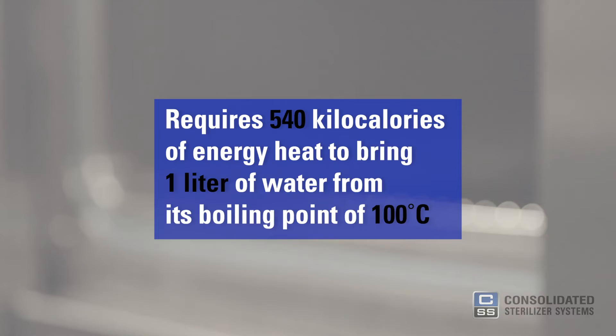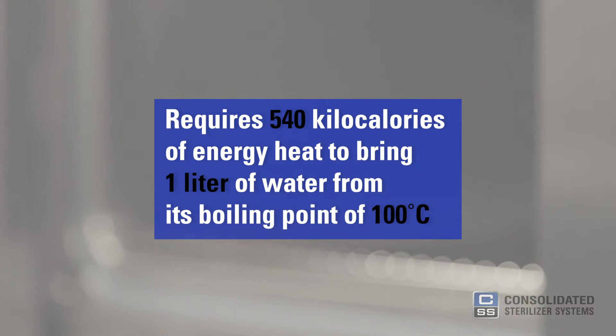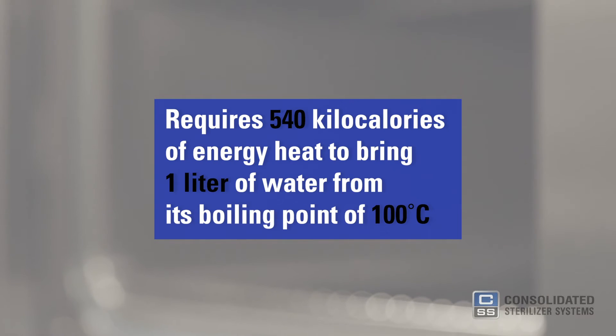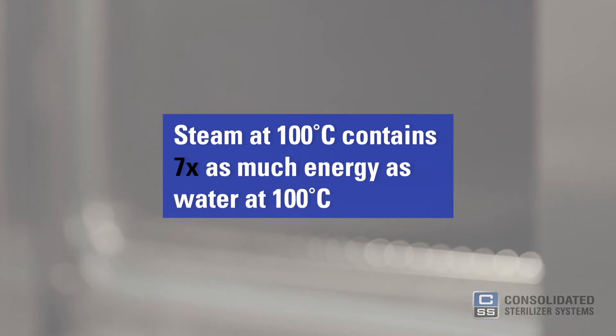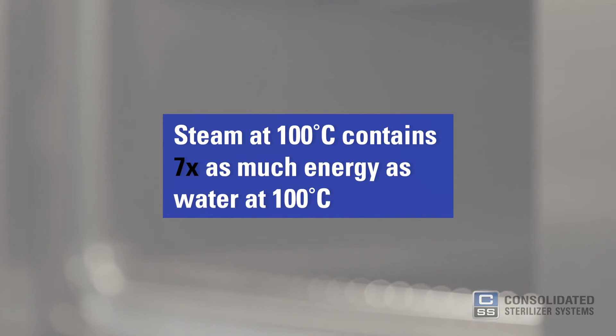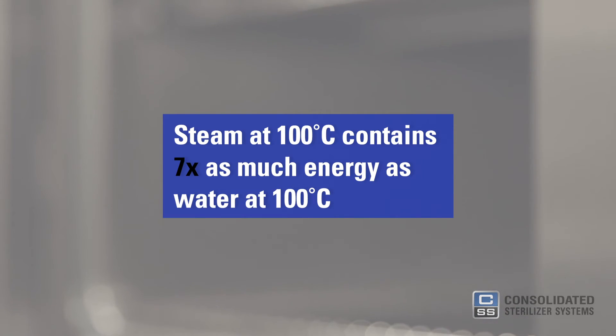It requires 540 kilocalories of energy to bring 1 liter of water from its boiling point of 100 degrees Celsius and make it steam, which means steam at 100 degrees Celsius contains 7 times as much energy as water at 100 degrees Celsius. All of this energy will be instantly transferred to the product being sterilized when the steam condenses on the object. This heats up cells far more efficiently than air at similar temperatures, which is why we use steam to achieve sterility.